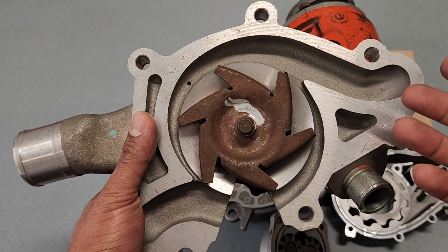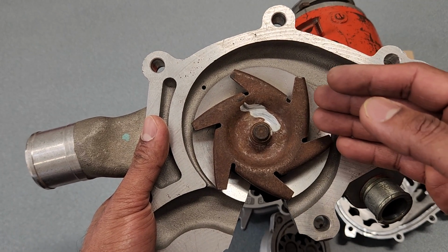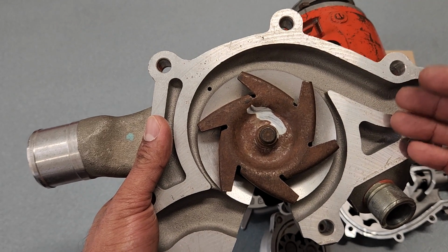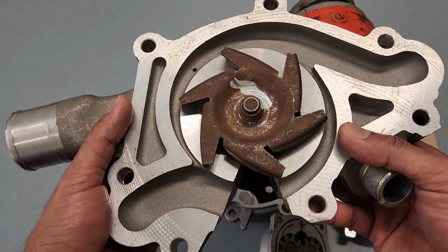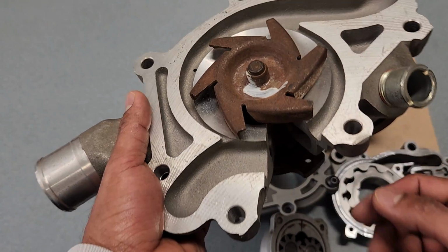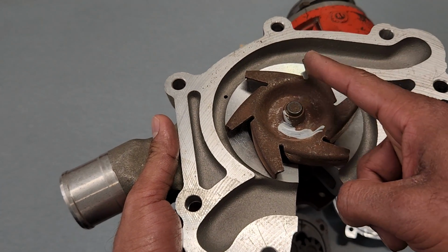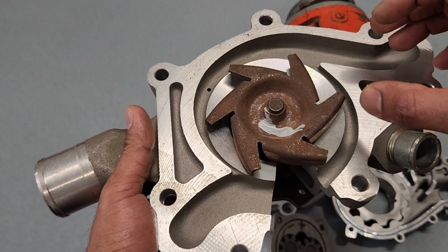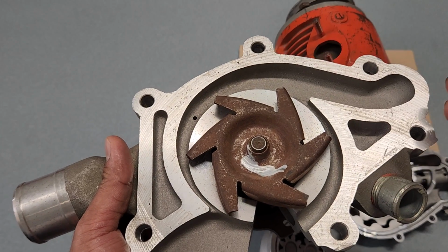However, energy is constant. You can't destroy or create it. You just convert one form to the other. So then that kinetic centrifugal energy converts into pressure energy, by increasing the area. So that's the key difference basically. By this rotation, vacuum or lower pressure is created inside the housing, and then on the outside flow, the output side, the volume starts to increase. So that drops the velocity by adding the pressure energy into the flow.